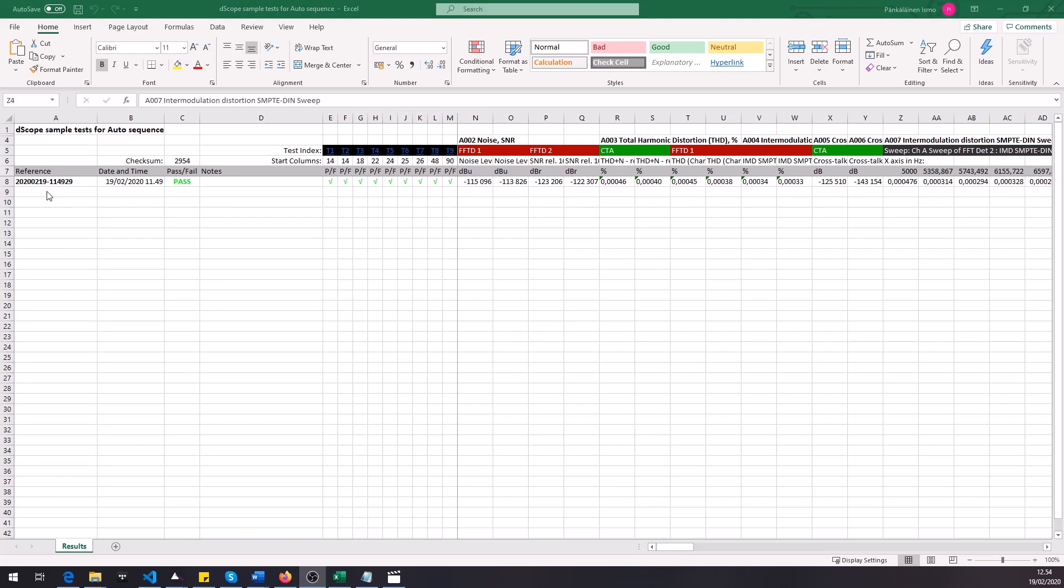And then if you would run the auto sequence on a loop then you would get a new row every time you start the loop. This would be useful for example when you want to make a long term measurement. So you could see when was the time that the test started to fail. And if you want more details then you need to use the HTML report to get for example the graphical results.